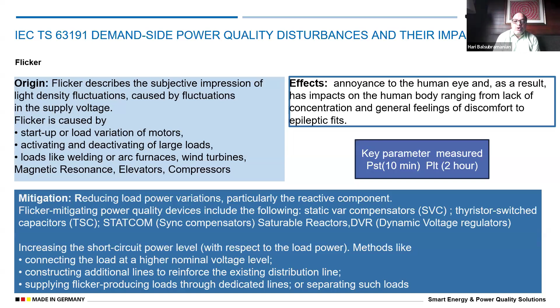The key parameters measured for flicker in these devices are PST and PLT. There are mitigation processes possible. Increasing the short circuit level of the system is one, as per the standard. You can also have VAR compensators and thyristor capacitors, or both, to control the flicker in the system.